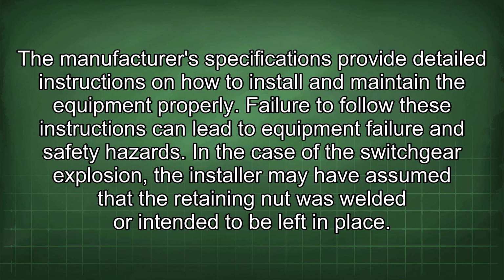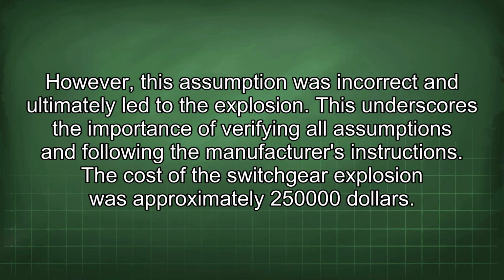In the case of the switchgear explosion, the installer may have assumed that the retaining nut was welded or intended to be left in place. However, this assumption was incorrect and ultimately led to the explosion. This underscores the importance of verifying all assumptions and following the manufacturer's instructions.